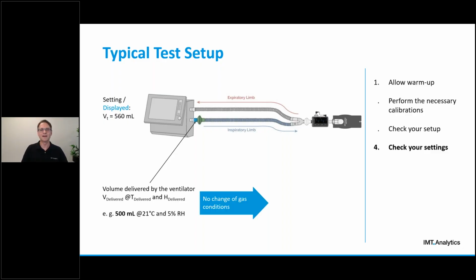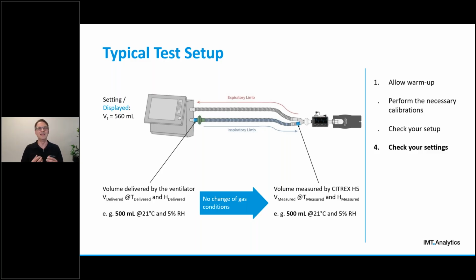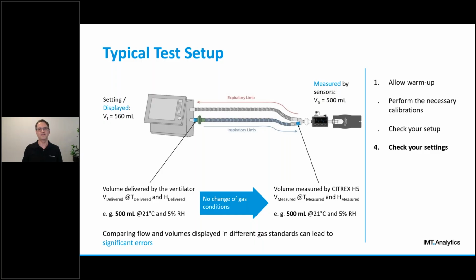But unlike in our previously discussed patient setup, in our test setup, the gas condition is not going to change, as there is no humidifier nor heated inspiratory limb. And therefore, our gas flow analyzer measures just the 500 ml actually delivered by the ventilator. And if that analyzer is set to the gas standard ATP, meaning it considers the actual temperature and humidity for the flow calculation, it also displays just the 500 ml as VTI. So what we do in this example is actually comparing volumes in different gas standards, BTPS on the ventilator versus ATP on the gas flow analyzer. And as you can see, that can lead to significant errors.